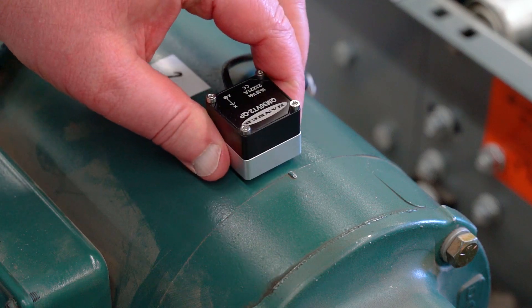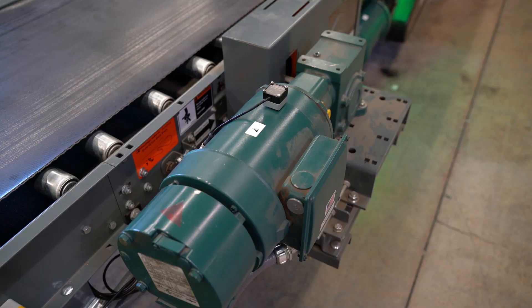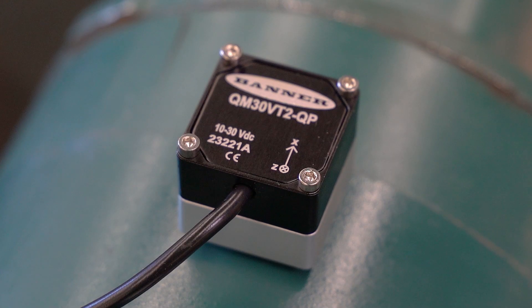When mounting the sensor to a motor, it is best practice to ensure that the x-axis is parallel to the motor shaft. The top of the sensor is marked with an arrow to indicate the direction of this axis.